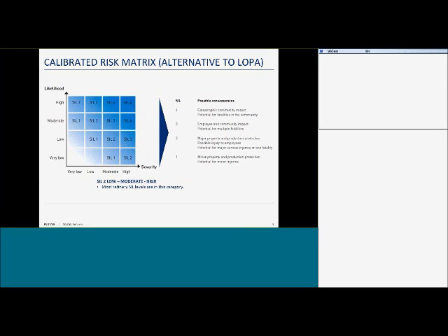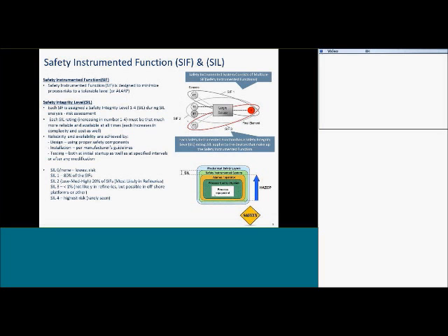And this is a little bigger blow-up of that calibrated risk matrix. Some of our customers use the calibrated risk matrix in conjunction with LOPA instead of as an alternative, in which case they may determine that everything SIL 2 and above they assign a LOPA to. Now, the reason they might do that is LOPA is very expensive. It's a lot of engineering. It's greater cost to the customer. So they may use these in conjunction with each other.